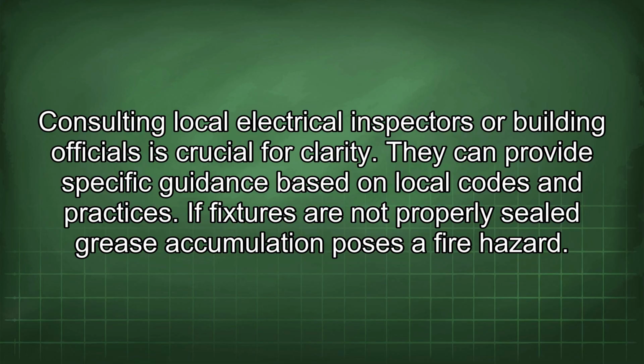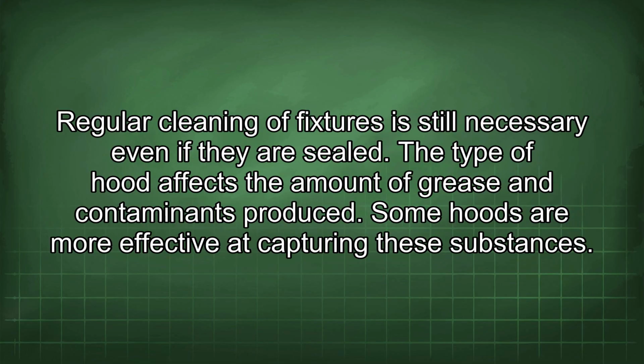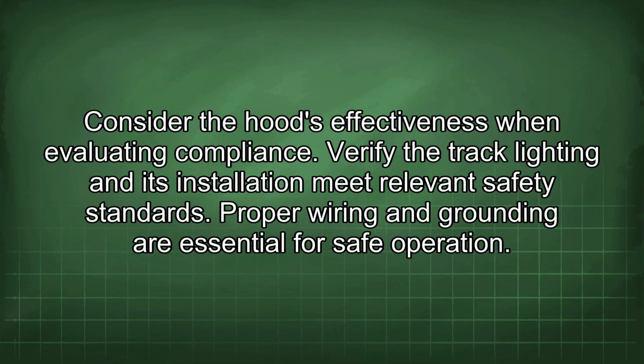If fixtures are not properly sealed, grease accumulation poses a fire hazard. Regular cleaning of fixtures is still necessary even if they are sealed. The type of hood affects the amount of grease and contaminants produced. Some hoods are more effective at capturing these substances. Consider the hood's effectiveness when evaluating compliance.